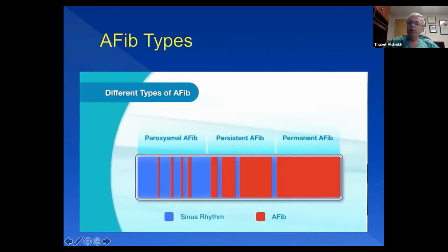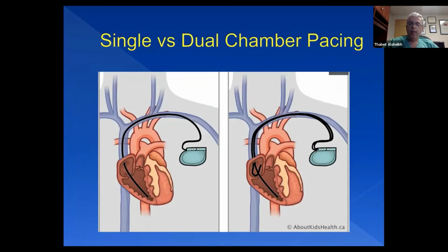When would we use dual chamber pacemaker, when would we use single chamber pacemaker? So single chamber pacemaker could be in the top chamber or the bottom chamber, but for the purpose of this talk, this single chamber goes to the bottom chamber, this dual chamber goes to the top and the bottom. To have dual chamber, that means this pacemaker can pace the top chamber and can pace the bottom chamber.